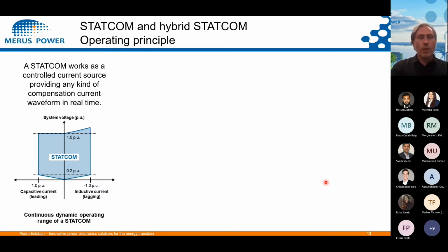In principle, I will not go too much into detail, but we have a control current source, and this current source is providing any kind of compensation current waveform in real time. So you can see here that this device, the STATCOM, can work in both sides, inductive and capacitive. It can provide these two currents.